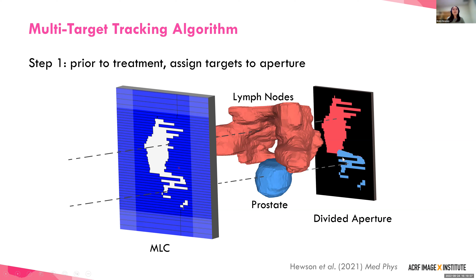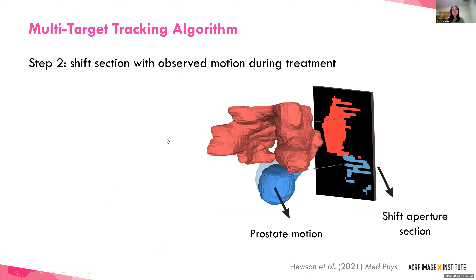So here we have an example where you can see the red section is the part of the aperture that's covering the lymph nodes, while the blue section is the part of the aperture that's covering the prostate. And we do this so that during treatment, when we do observe motion in one of the targets, we can then shift that section of the aperture accordingly to match that target's motion. And then we recombine those aperture sections back into a deliverable adapted aperture once we take into account the physical MLC leaf constraints. So you can see here what we've resulted in is an MLC aperture where one section's been adapted independently for the prostate, while the other aperture for the lymph nodes has remained as it was.